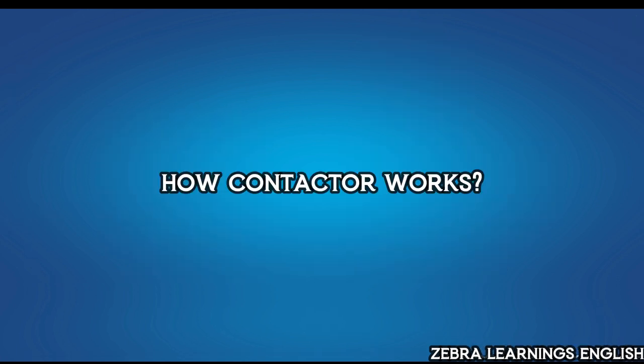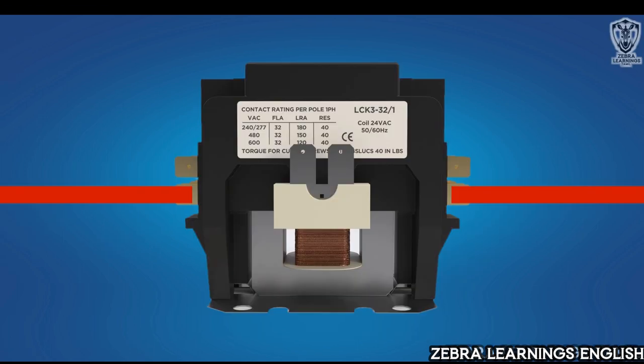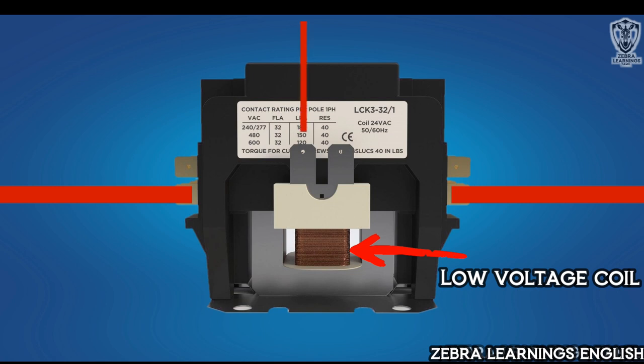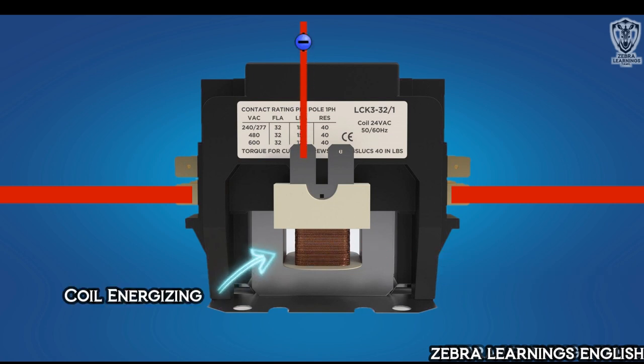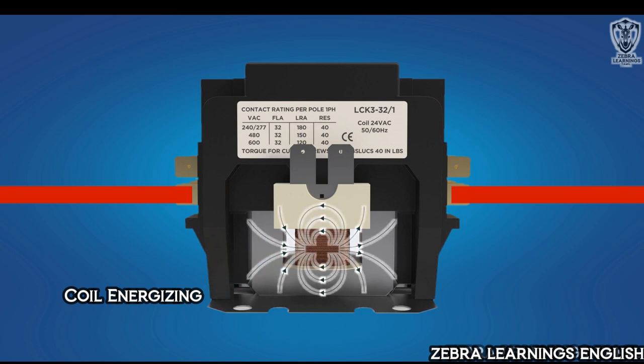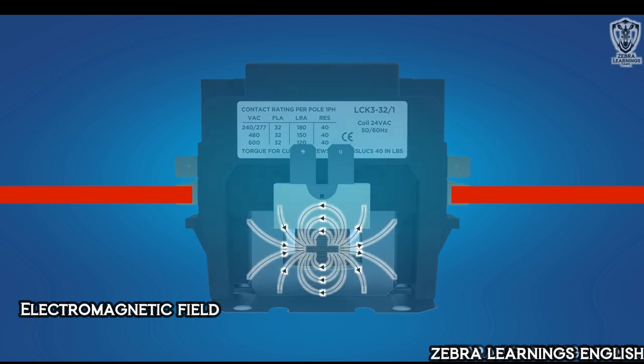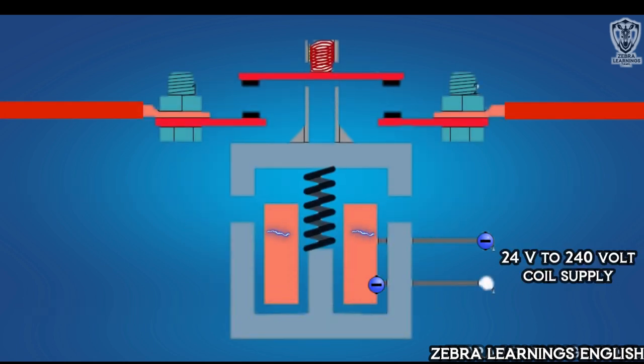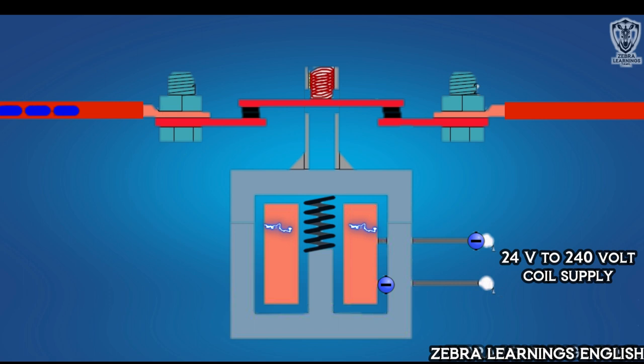Now, let's see how contactor works. Contactor has a low voltage coil. When 24-volt power is supplied to this coil, the coil energizes and an electromagnetic field is generated in the coil. By this magnetic field, when the terminal in it is attracted and connected, the power supply will start to flow through it.